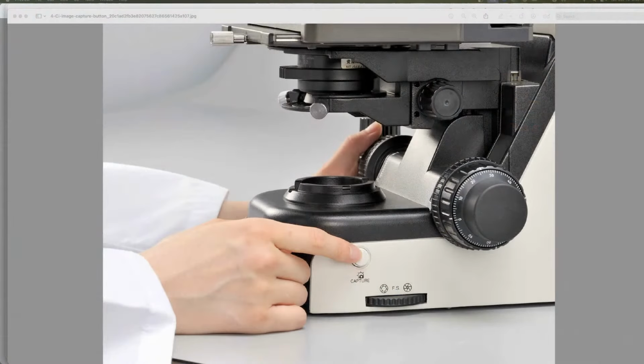Inside here there is a, let me see if I can find it. Right inside here, I don't know if you can see my pointer. Inside the condenser, right under the stage, there is an iris that you can open and close, and it is that condenser aperture, that diaphragm, that forms the second conjugate level.